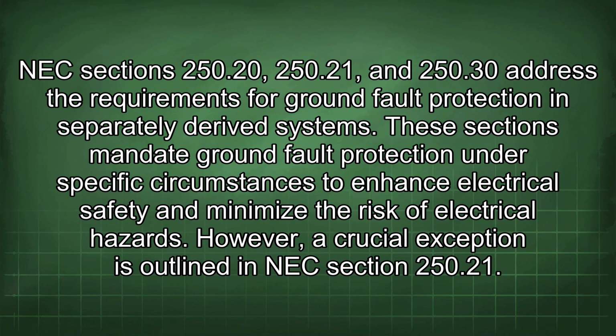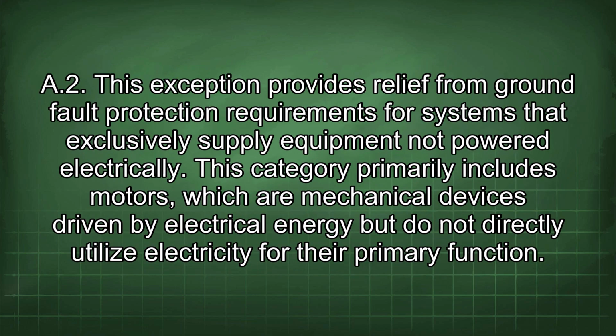NEC sections 250.20, 250.21, and 250.30 address the requirements for ground fault protection in separately derived systems. These sections mandate ground fault protection under specific circumstances to enhance electrical safety and minimize the risk of electrical hazards. However, a crucial exception is outlined in NEC section 250.21 A2. This exception provides relief from ground fault protection requirements for systems that exclusively supply equipment not powered electrically.